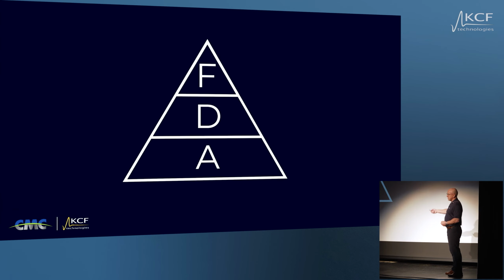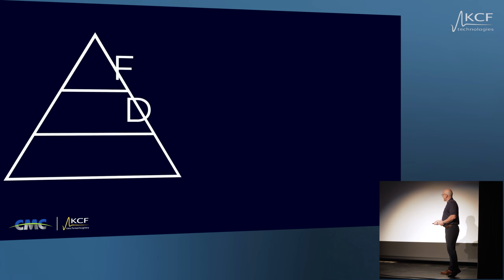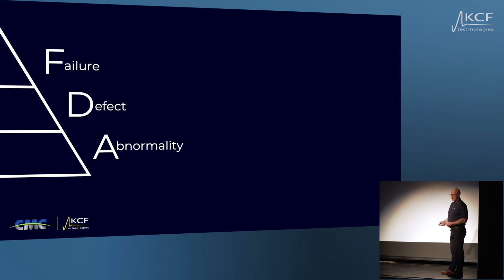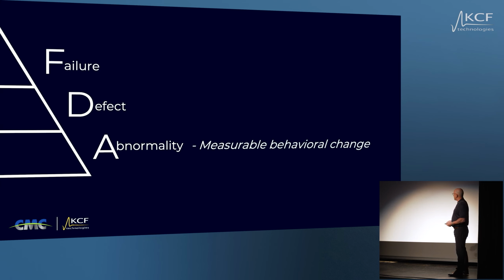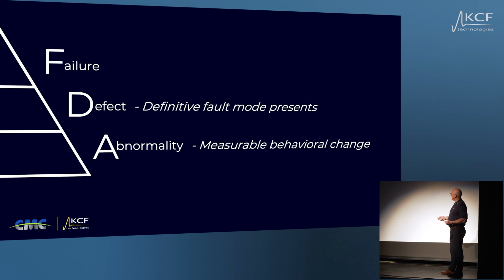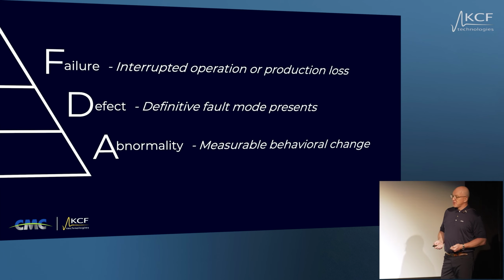So don't read this from the top down, nothing to do with the FDA. Read it from the bottom up. And this is our abnormality, defect, failure triangle. So the definition of an abnormality is a measurable behavior change. A defect is a definitive fault mode that's presented itself. And a failure is an interrupted operation or production loss.